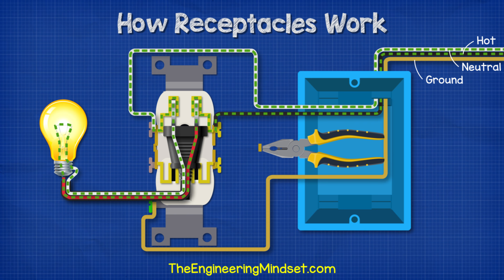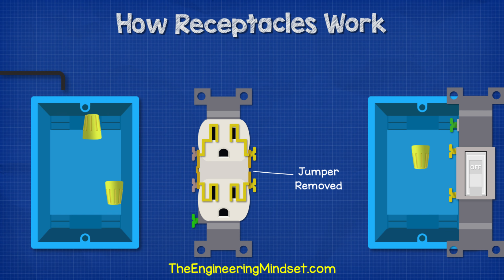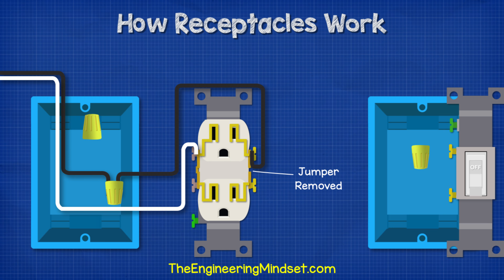One application is when using switch receptacles like this circuit here, which allows half of the receptacle to remain hot while the other half is controlled by a switch. For this, we bring the hot wire in and connect this to the wire nut. We then run another hot wire from there and over to the top hot terminal. We can then run our neutral wire back to the service panel. Of course, we need to also include our ground wires too. If we powered this circuit, then only the top half of the circuit would be hot. The lower half would have no power.